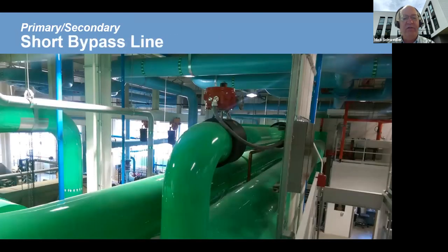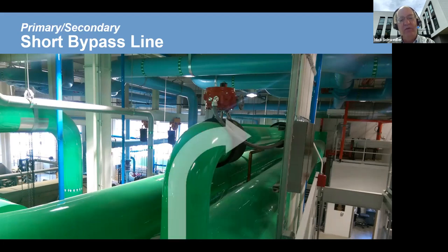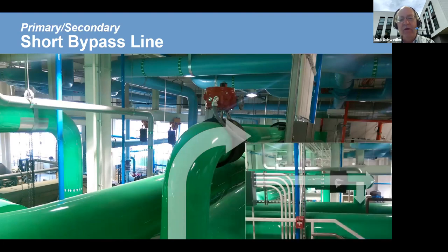So in a case like this, this is from a university project. What they did, we have our chilled water supply pipe, our chilled water return pipe, and they put some elbows in here. So they took the water flow rate out of the supply side, took it down the pipe, put it over to another couple elbows and back into the return side. So what this does, this imposes a small pressure drop in the system, but it keeps water from short circuiting because of the short bypass line. You usually want your bypass line to be 10 pipe diameters or larger so that there's a small pressure drop, but not too much.